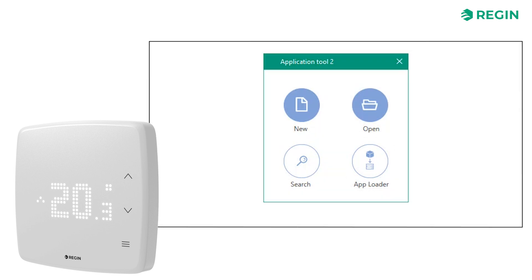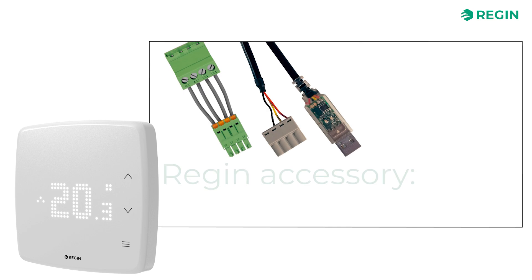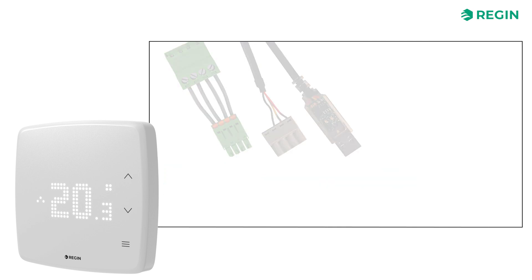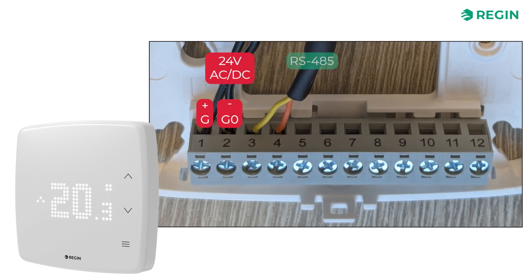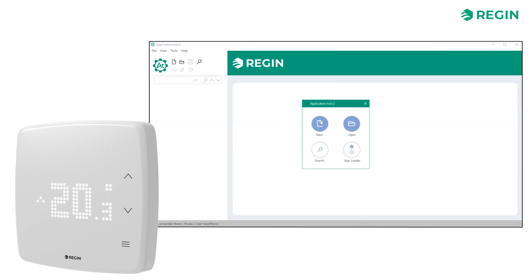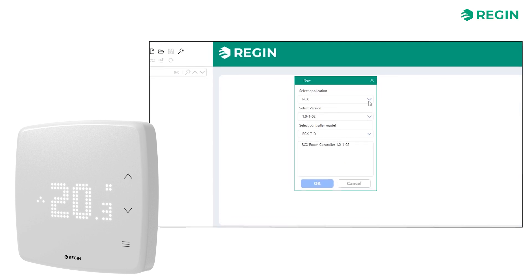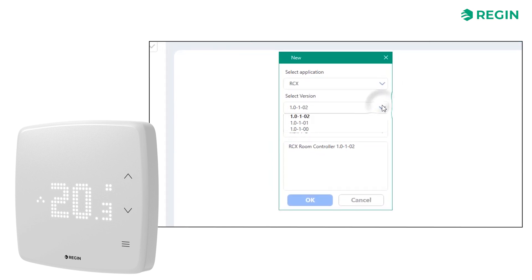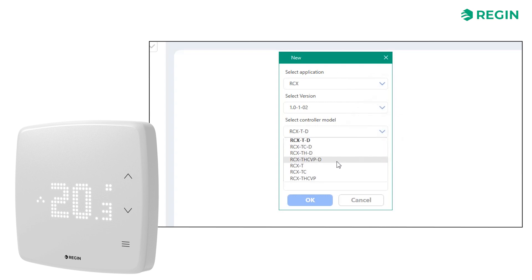Let's start by connecting a Regin RCX using the serial interface. Attach the data wires like this — Negative A to terminal 3 and Positive B to terminal 4. Next, we start a new project and select the appropriate application, software version, and controller model we are working with.